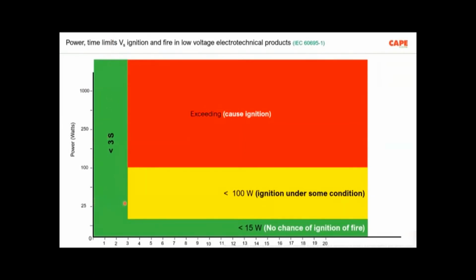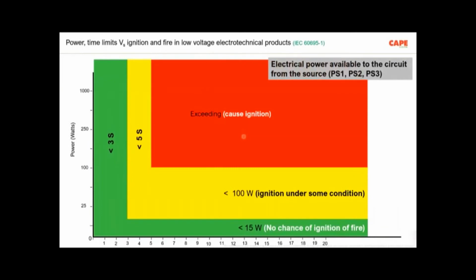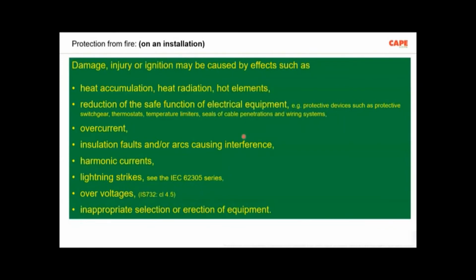If we are able to limit the fault to less than 15 watts within 3 seconds, then the chance of ignition of fire is less. In simple words, if your MCB trips within 3 seconds, the fire chance is less. Similarly, if the protective device is operating within 5 seconds, ignition is possible only under some conditions. These are some of the concepts considered for designing an electrical apparatus and an electrical circuit with respect to safety. So based on this, power source classification comes into picture. I explained this in my last class.